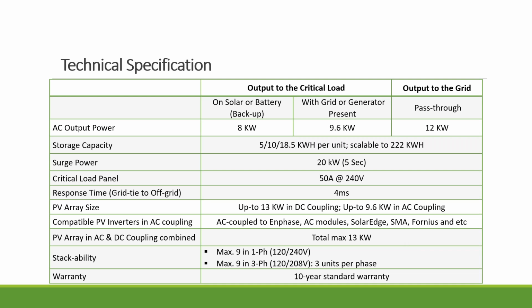It also has a built-in transfer relay and an amazing surge capacity. You can see 20 kW for 5 seconds. The Schneider also has very nice surge, 12 kW for 60 seconds. That's very important when you choose a hybrid inverter, because otherwise, just to give you an example, the Tesla Powerwall is a 5 kW inverter and can only surge 7.5 kW. So it's only 33 amps. It's very small.